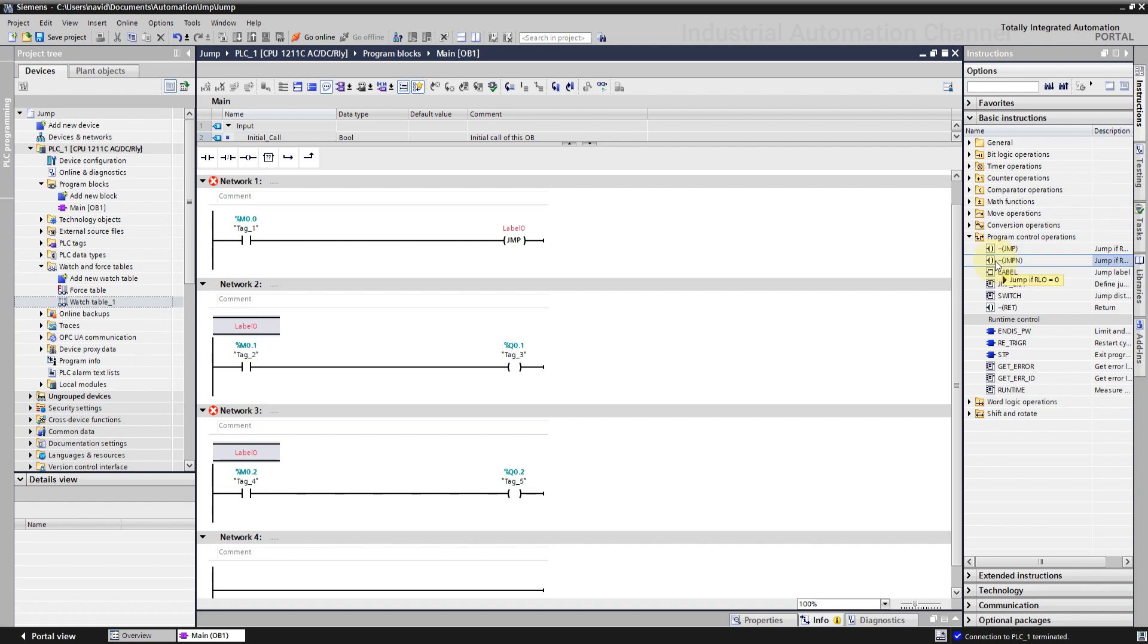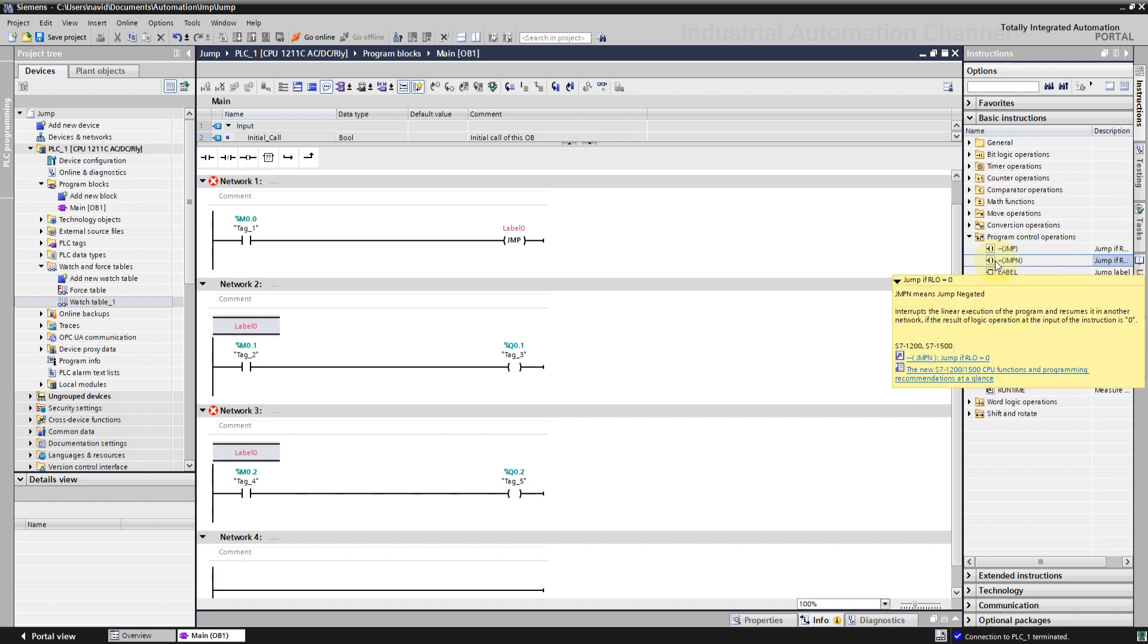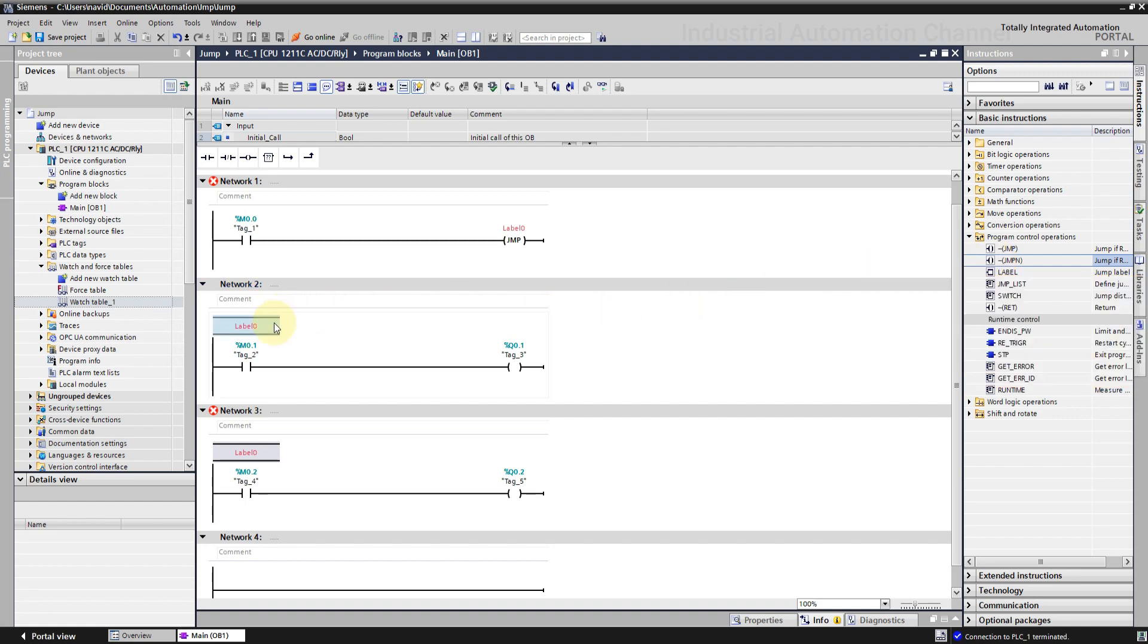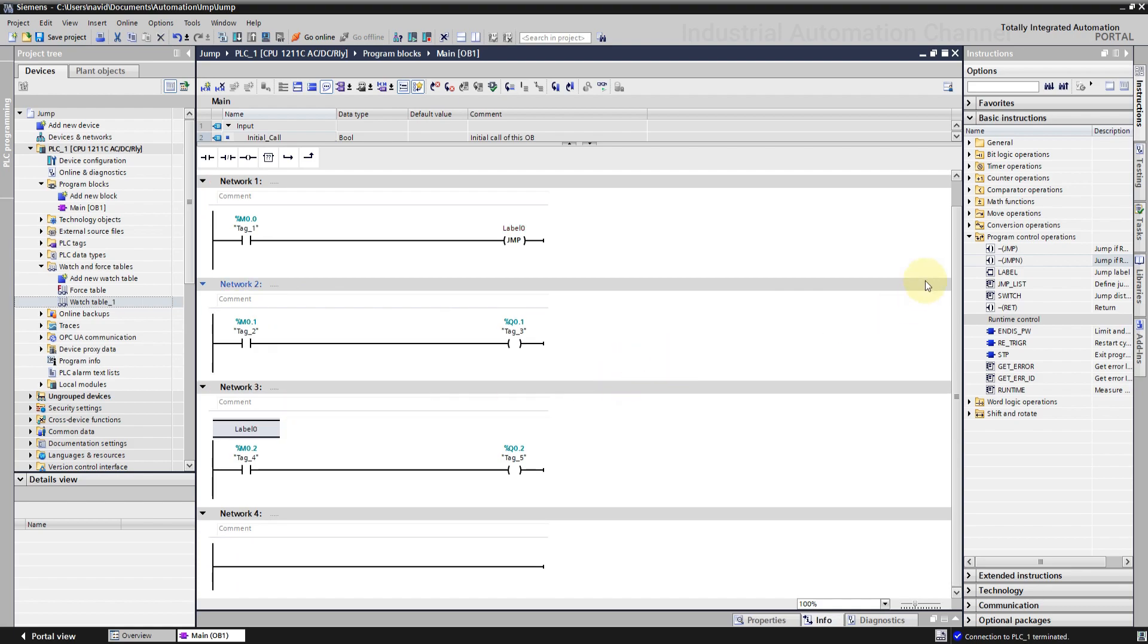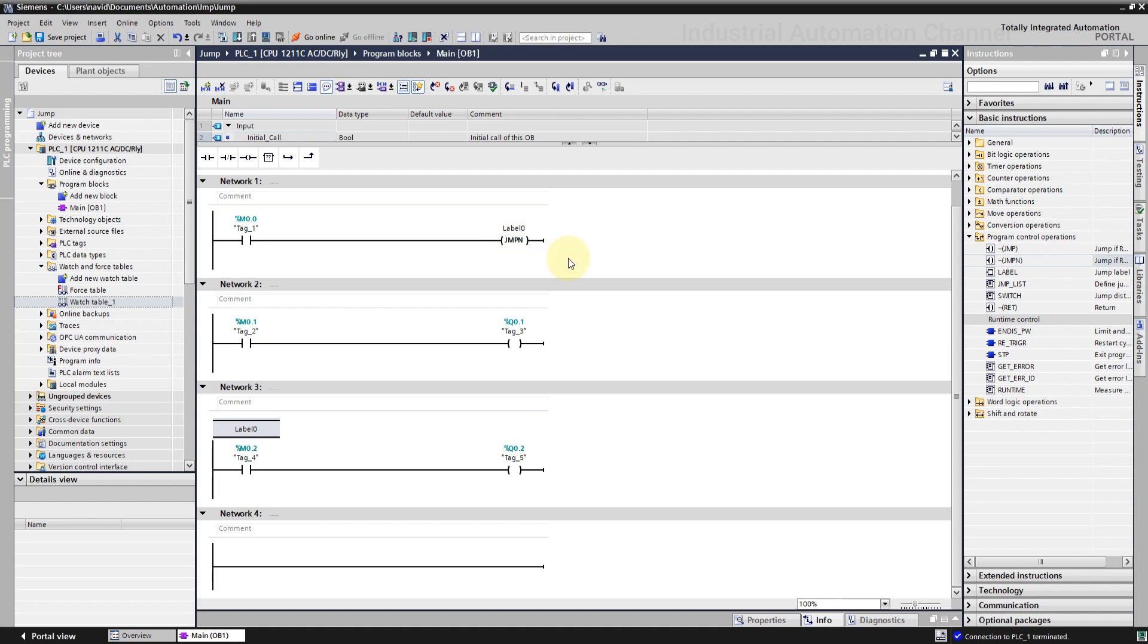Okay, the second one is jump not. This is exactly the reverse of a jump. With jump, when we activate the instruction, the program scan will jump to the label. But with jump not, when the instruction is not activated, the execution is jumped to the label. Let's change the jump to jump not. Download the change.